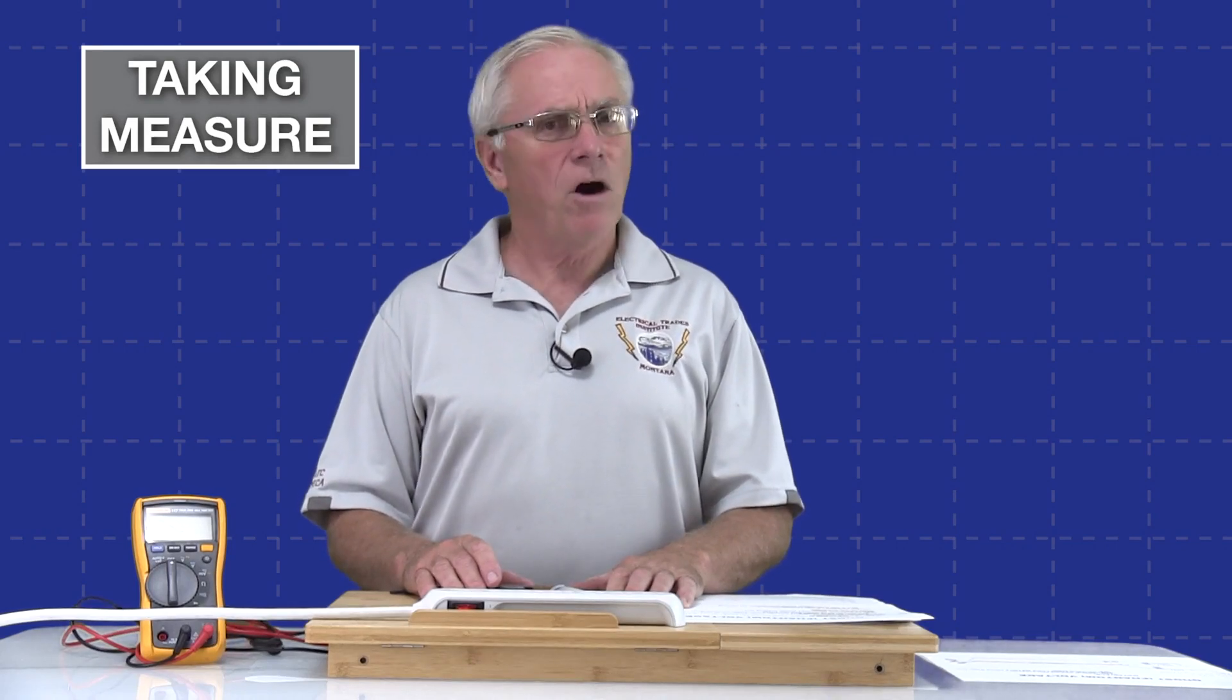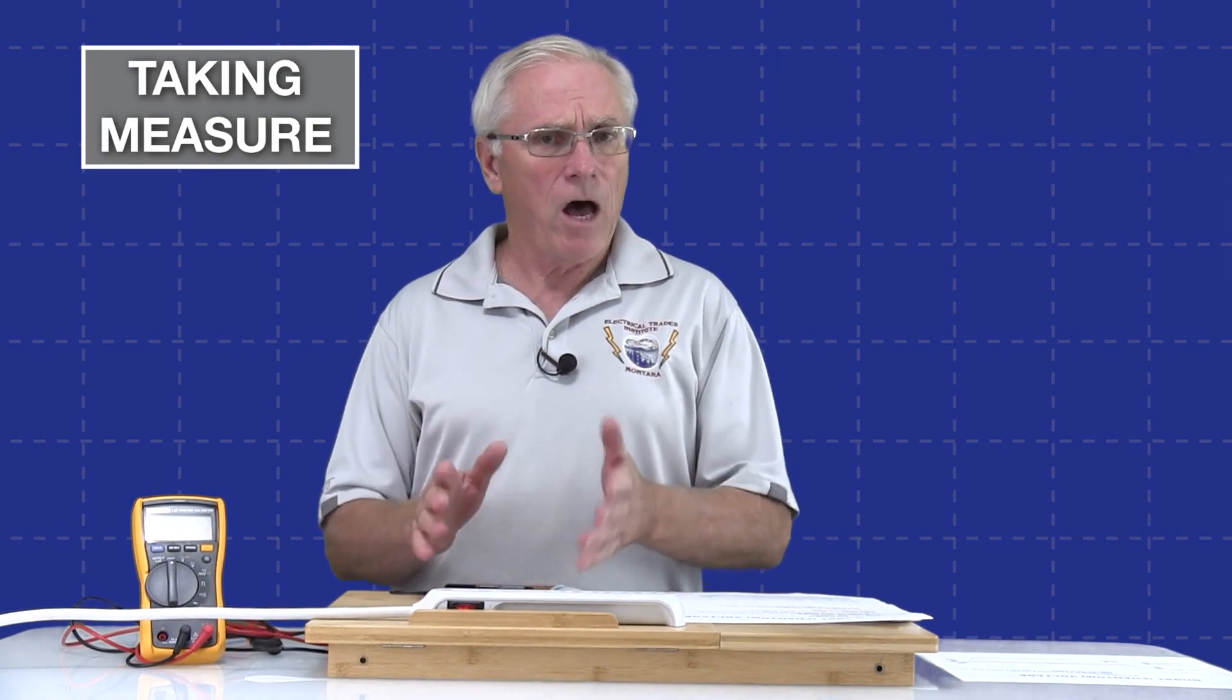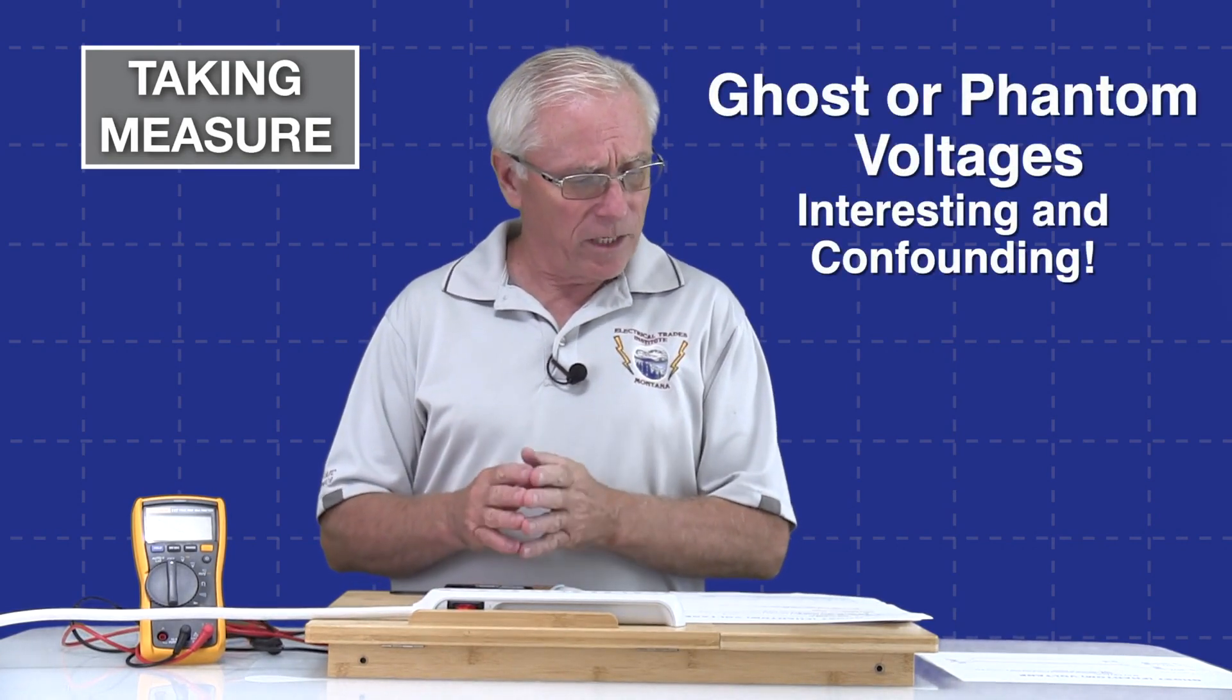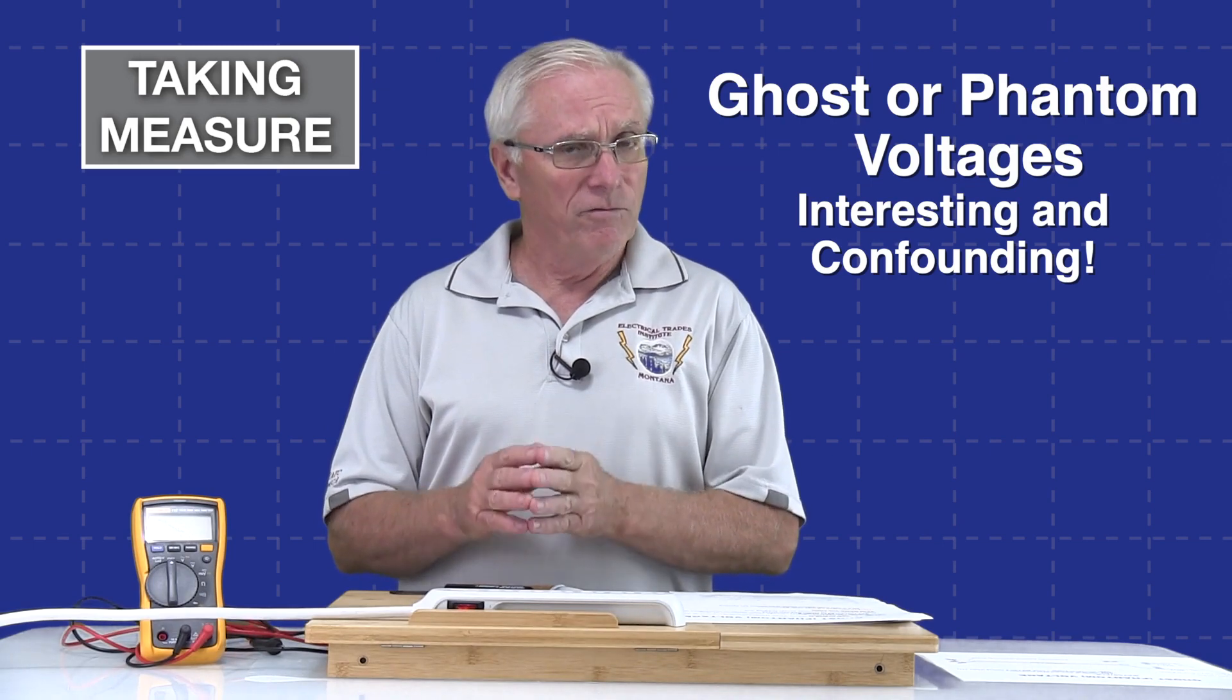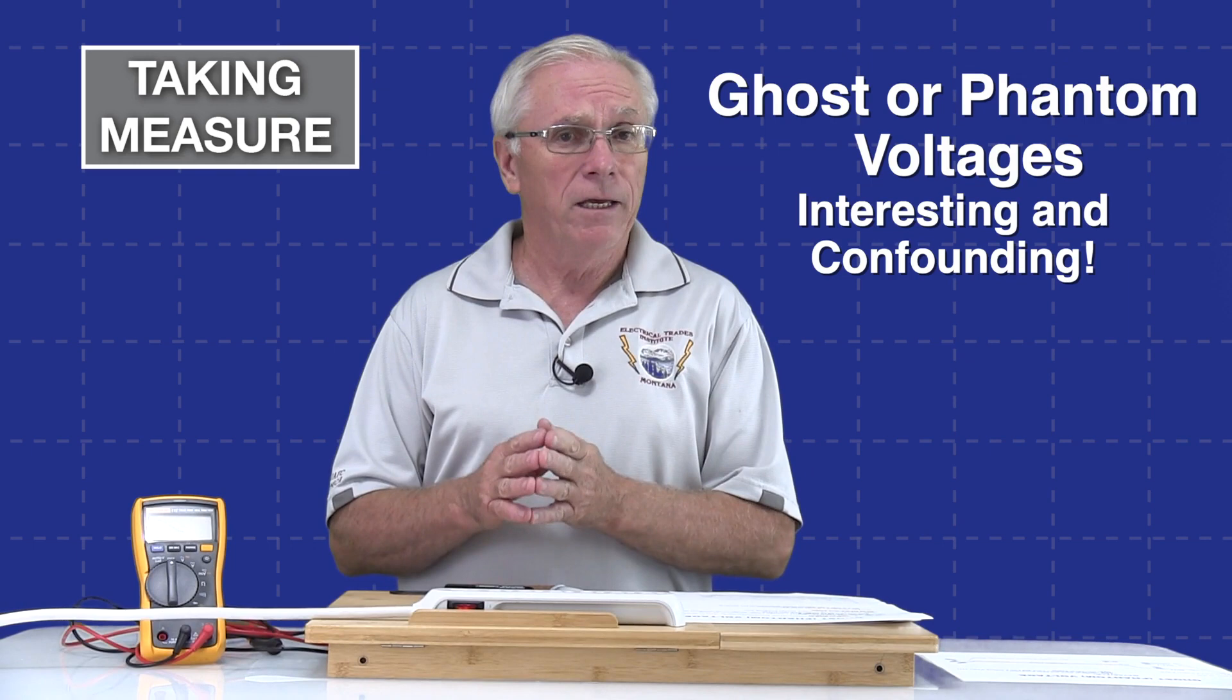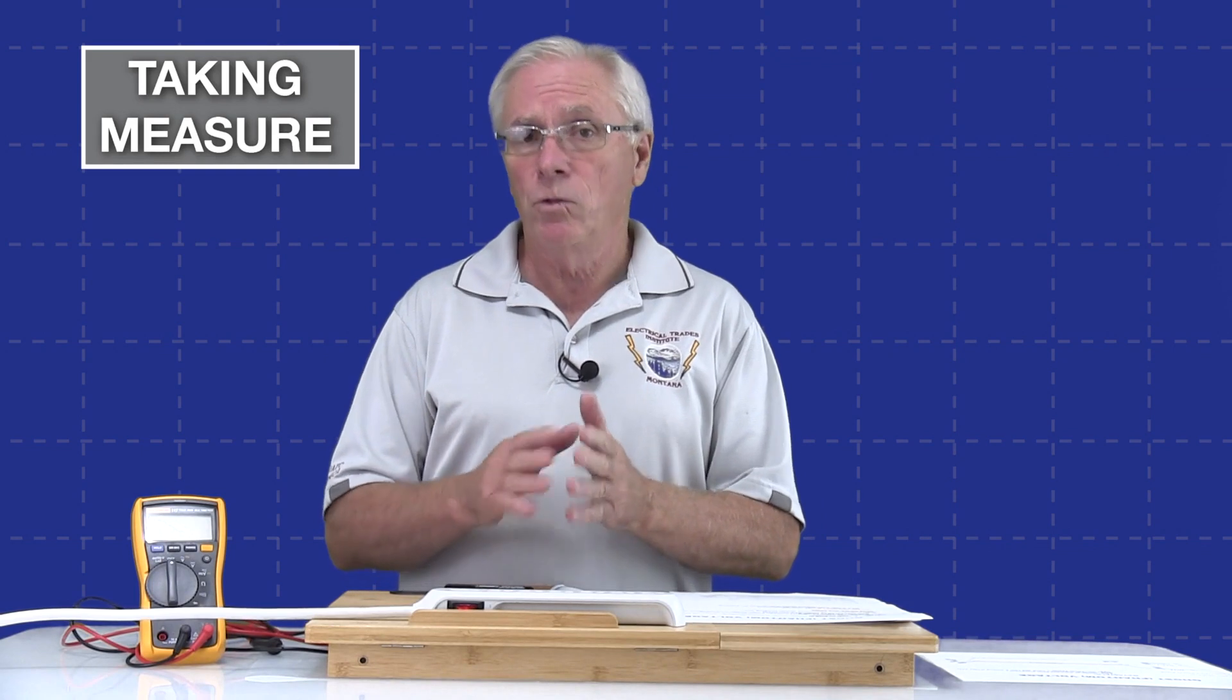One of the more interesting and confounding problems when troubleshooting electrical circuits is the phenomenon of ghost or phantom voltage. On AC circuits you will sometimes see apparent voltages that are as high as the circuits you're working with, and really there's nothing there at all. So we're going to explore that a little bit today. We'll talk about it first, explain how it works, and then we're going to have a lab and use various test instruments to see what happens.